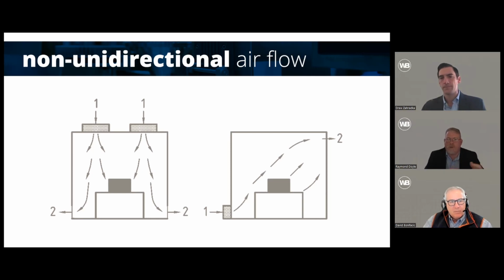As soon as you have people moving around, there becomes a little bit of turbulence. But the intent is, at a steady state, that airflow is going to go straight down through the floor. We've done the same thing in some aerospace applications where you have a huge high bay space, and we'll talk about this again later, where we have a sidewall condition where it's left to right, where they'll have large satellites or equipment in these large spaces, and the air will flow from left to right and then go out the other side, similar to the previous slide.